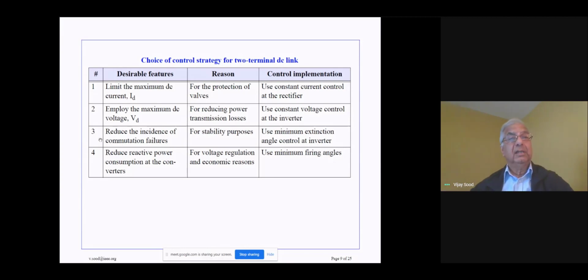The third requirement is to reduce the incidence of commutation failures. In line commutated converters, a commutation failure is a fairly frequent incident, and we want to make sure that we reduce that as far as possible, obviously for stability purposes. In order to minimize the incidence of commutation failures, the control methodology that is suggested is to use a minimum extinction angle control at the inverter. So if we can keep a minimum extinction angle, then the possibility of commutation failures will be reduced.